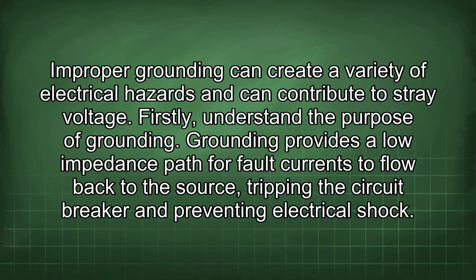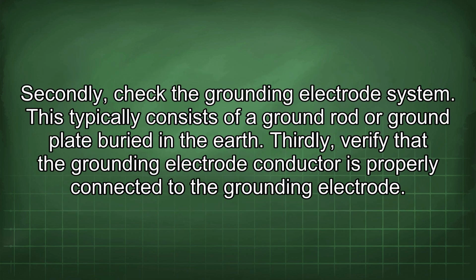Improper grounding can create a variety of electrical hazards and can contribute to stray voltage. Firstly, understand the purpose of grounding. Grounding provides a low impedance path for fault currents to flow back to the source, tripping the circuit breaker and preventing electrical shock. Secondly, check the grounding electrode system. This typically consists of a ground rod or ground plate buried in the earth.